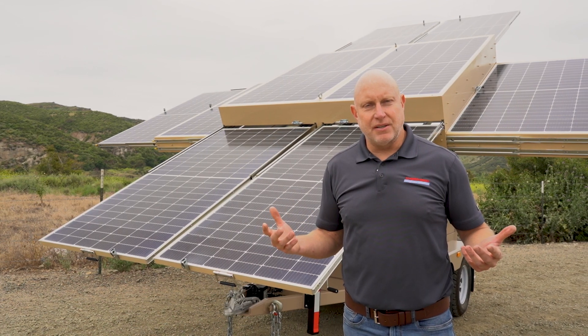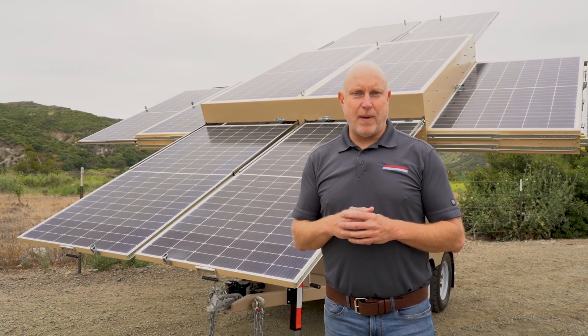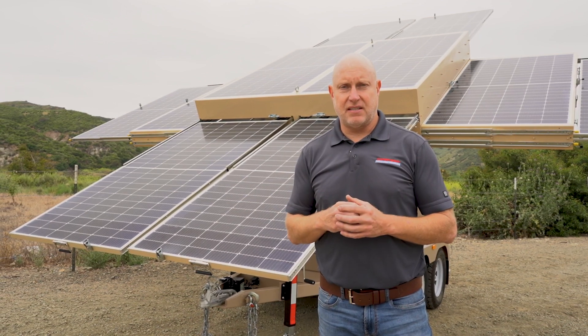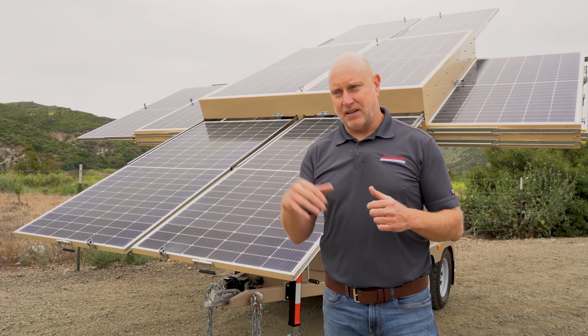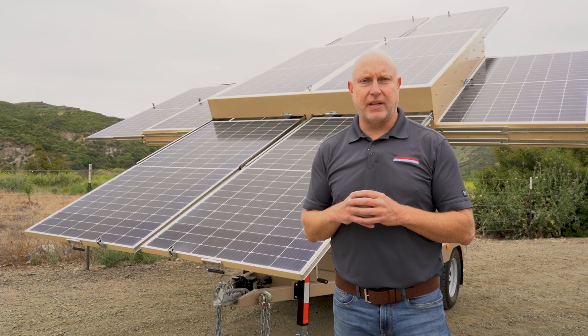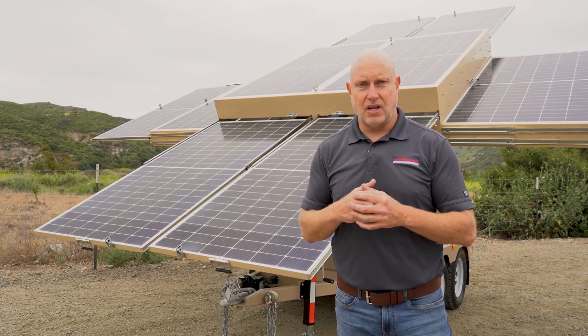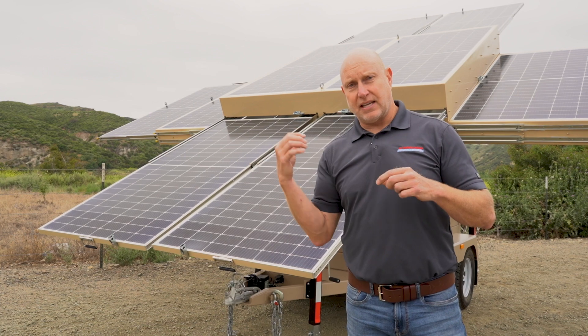So where is this used and how is it used? The 12 kilowatt generator is enough to power a house with air conditioning — probably about a 2,500 square foot house with air conditioning — for up to 10 days without refueling. We can also run a cell tower up to 9,000 watts continuous on this unit with about 10 days between refueling. The system works with solar powering during the day and diesel at night with battery storage, achieving about 50 to 60 percent diesel fuel savings by using the tribrid solution.